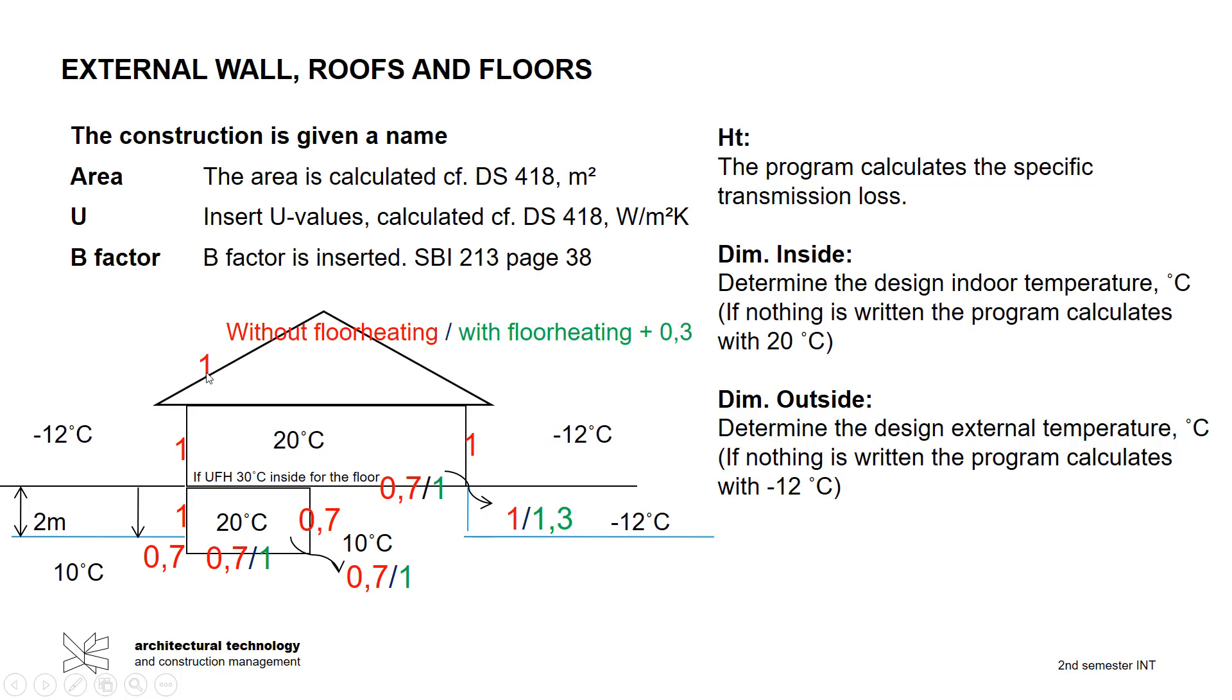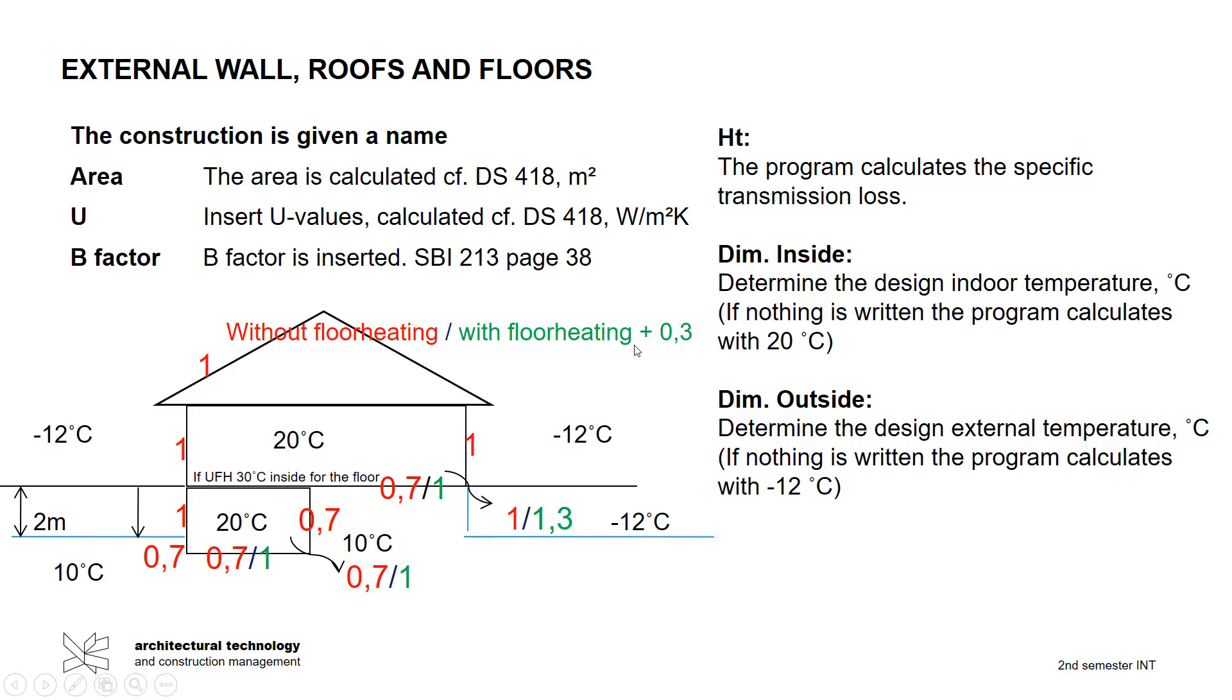Then we have this, so there it's 1 for the roof and for the wall it's always 1. It can be different when we have the floor because if we have underfloor heating we will have 30 degrees in this construction. And you can see also here the green ones is with underfloor heating, and that means we have to add 0.3 to the B-factor.